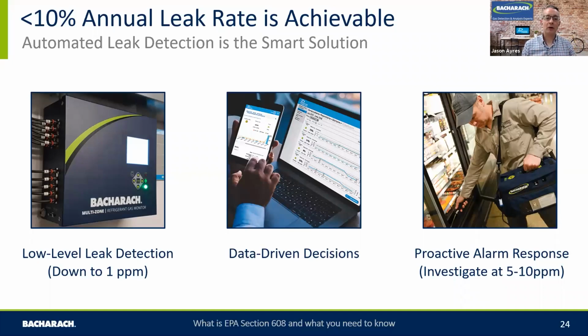Those equipments work great on their own. How can we elevate that detector and that information? Connectivity is key to that, allowing you to retrieve that information and use the data proactively within your enterprises to see and be aware of leaks sooner, manage your engineering teams better, and direct them better to the source of the problems. Data-driven systems and solutions provide part of that overall solution. And also alarm and response as well. We talk about being able to detect to 1 ppm, but it's also about looking at the alarm set points. Traditionally, we've been looking at alarms around 2, 3, 4, 5,000 ppm.